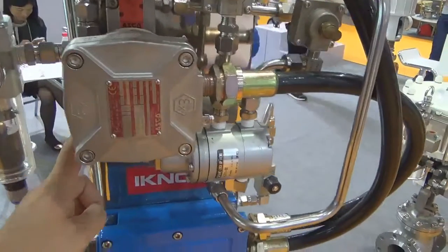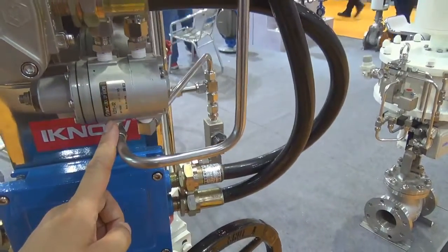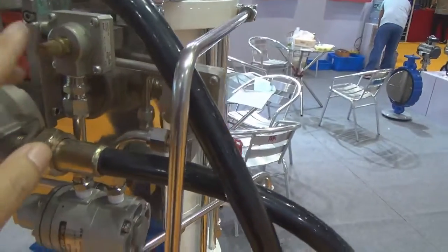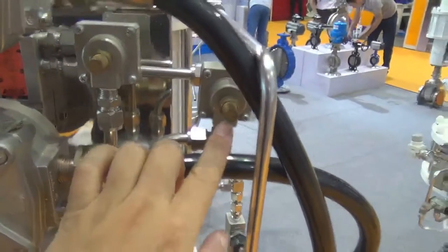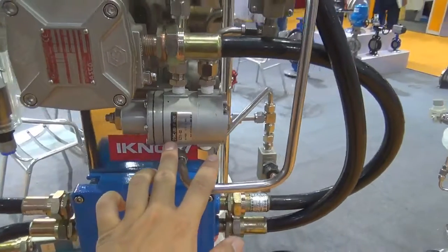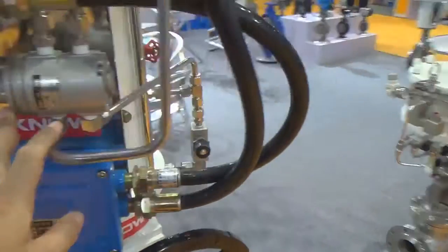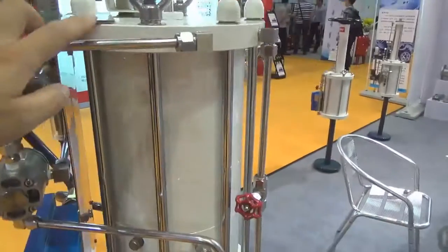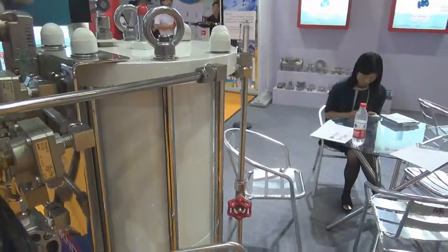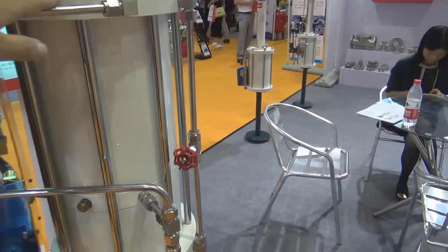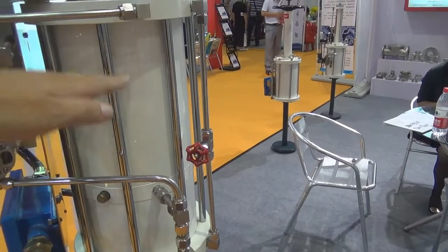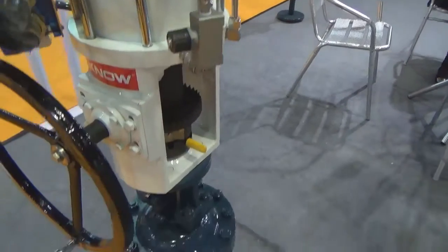When the system has gas, the lock valve will open, and then the solenoid valve has two-way flow outside. This is one way, and another. The two ways will flow to the lock valve, because the lock valve is already opened by the gas. So we have two-way flow to the cylinder, upside and downside. So we can use the solenoid valve to change the gas flow to the upside or to the downside. So we can control the piston inside the cylinder to move up and down to control the valve.